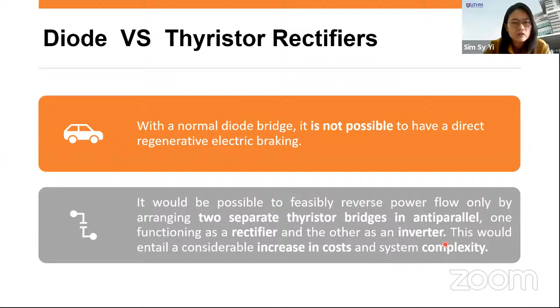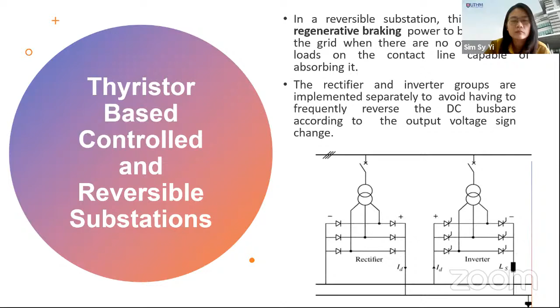In the reversible substation, this allows the regenerative braking power to be fed back to the grid when there is no other traction load capable of absorbing it. So as mentioned, one bridge serves as a rectifier as usual, and another with the thyristor serves as an inverter. This is what happens in the substation.